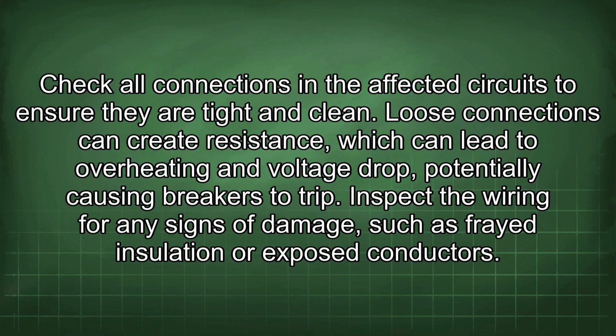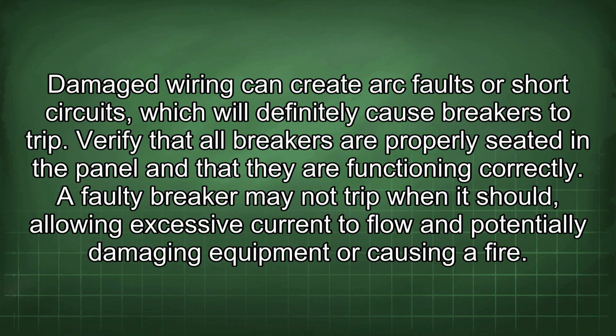Check all connections in the affected circuits to ensure they are tight and clean. Loose connections can create resistance, which can lead to overheating and voltage drop, potentially causing breakers to trip. Inspect the wiring for any signs of damage, such as frayed insulation or exposed conductors. Damaged wiring can create arc faults or short circuits, which will definitely cause breakers to trip.